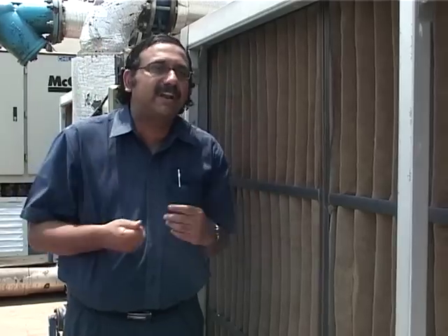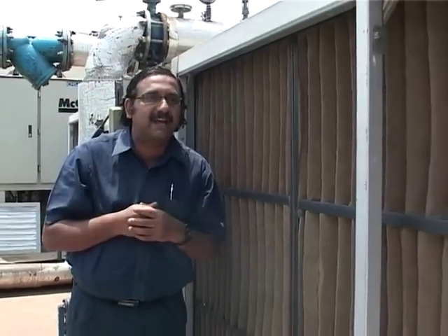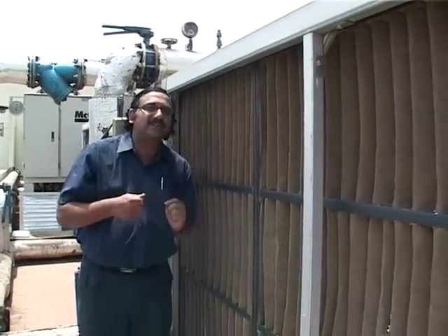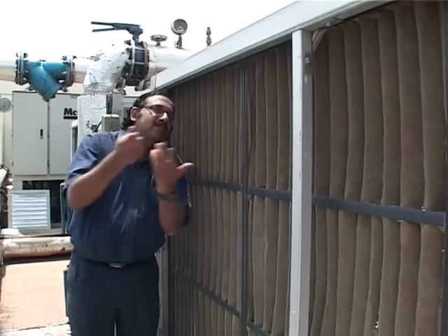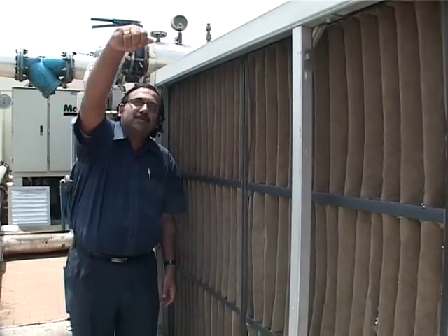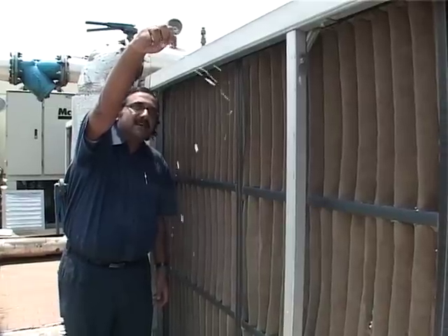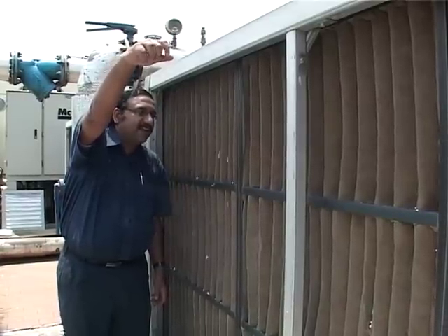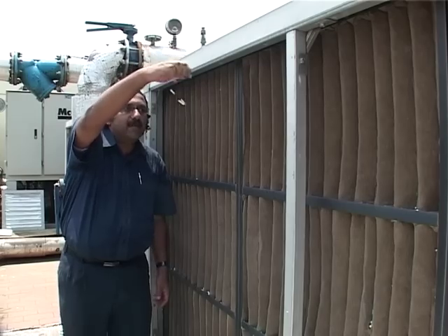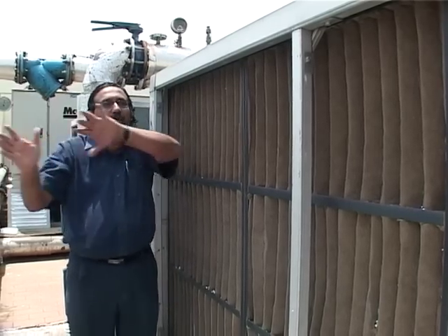Just to tell you how the airflow is in this particular region, if I throw some light particles here, they will move in the direction of the filter because air is getting into the filter unit. So just see, these thermocol particles are moving in the direction of the filter units. This tells you that there is an airflow in this direction.